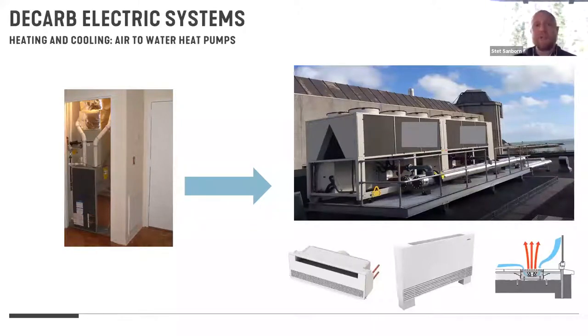Now, most of our projects are coastal California, with a little bit in the Inland Empire, in the valley, but these work really well for our climate zones. Our temperatures on the coast tend to bottom out around 30 degrees Fahrenheit outside air temperature. And these do great at 30 and above. We do start to run into some defrost issues, and I'll talk about that in a little bit.